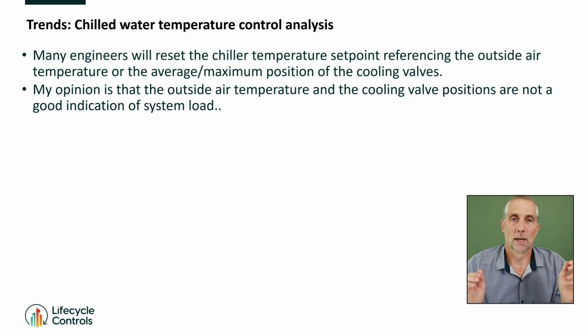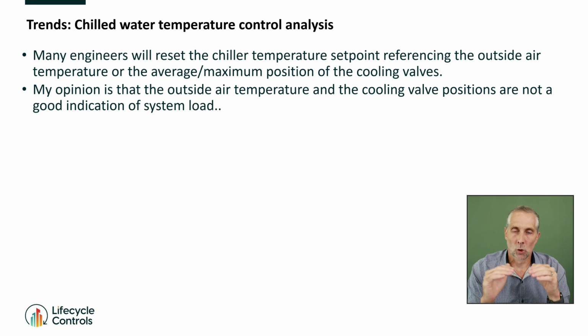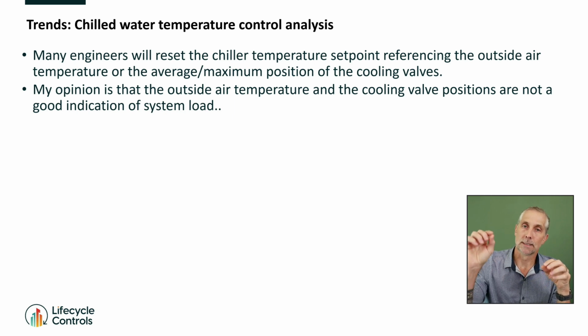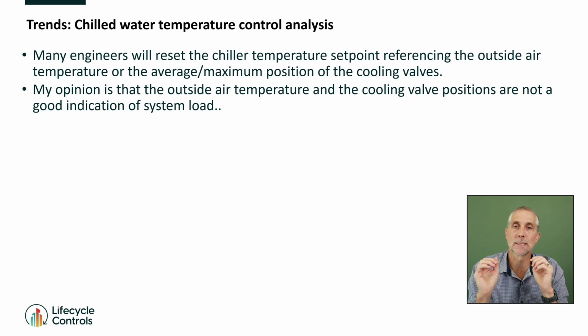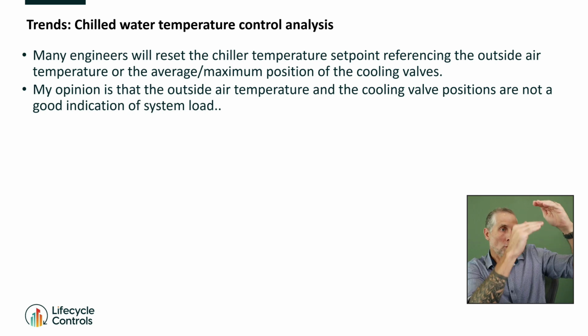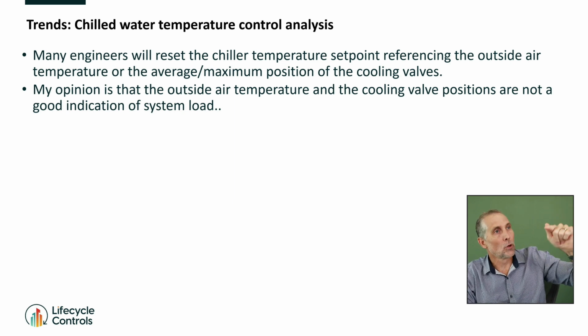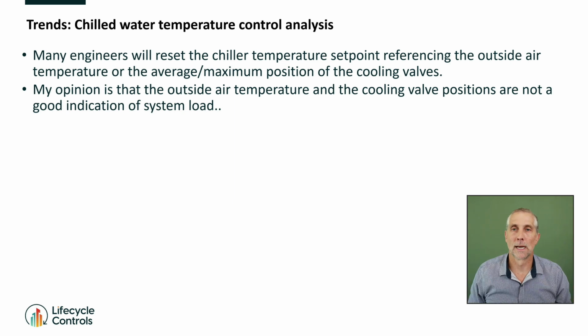So when you look at a chill water system with a chill water system pressure set point reset, you will usually see that the valves stay in the same place. So the control strategy might say, reset the chill water pressure set point up and down to maintain the most open or the second most open or the fifth most open cooling valve at 90%. That's the control strategy. So if you've got the third highest cooling valve and you look at all the cooling valves, the third one is going to be on the set point, 90% open position.